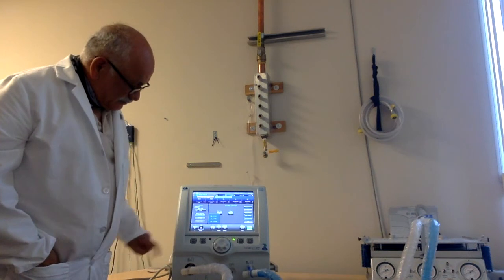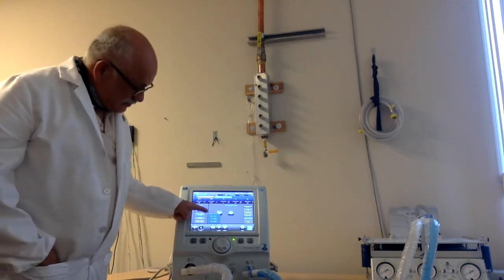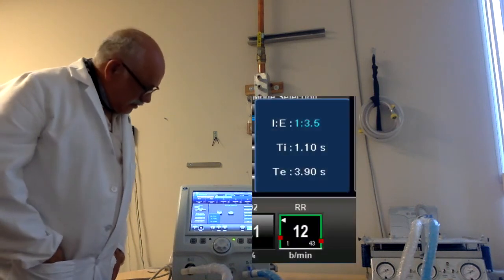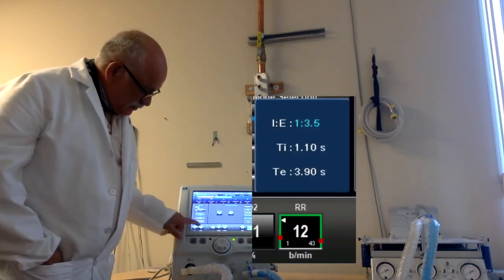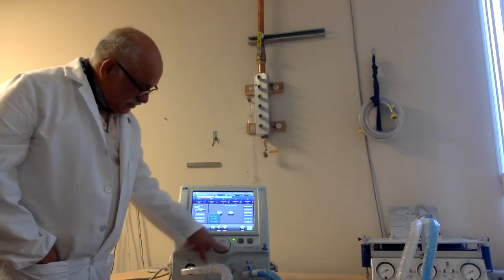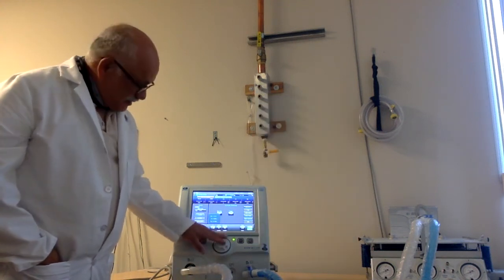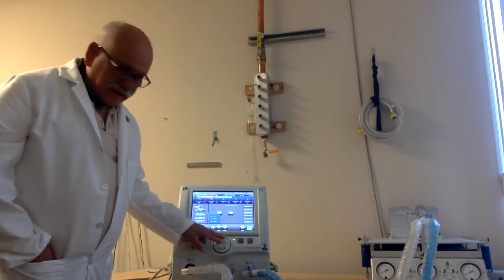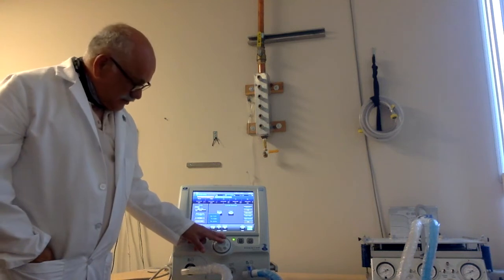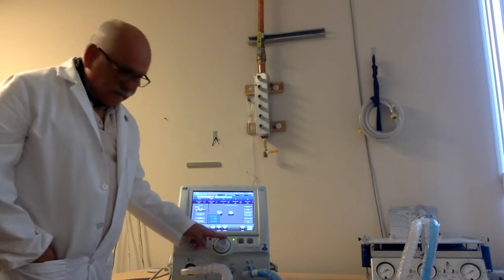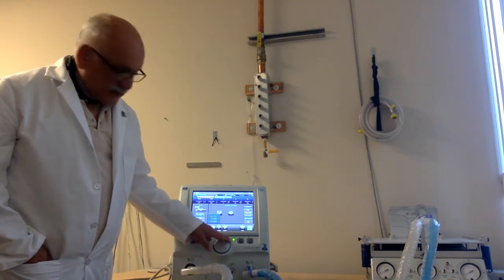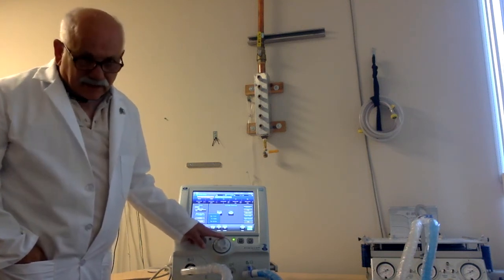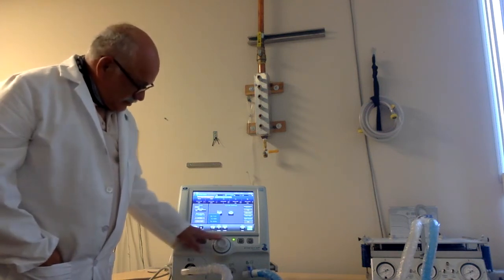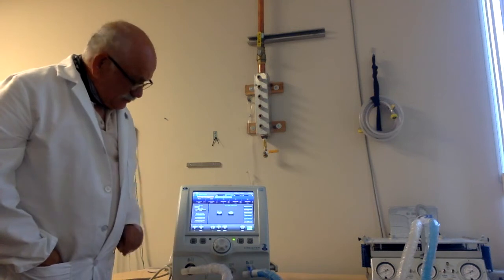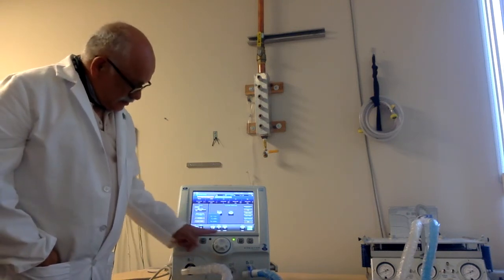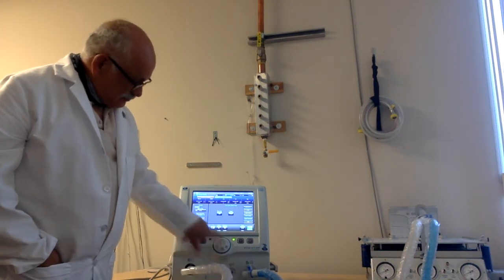I'm going to choose a rate. Now, when I want to choose a rate, you might notice that you see IE ratio, the time of inspiration, and the time of exhalation. As I rotate my choice of rate, I'm presented with the impact that will have on these variables: IE ratio, time of inspiration, and time of exhalation. This is important for physicians and therapists as they set a ventilator, to look at the impact prior to enacting it. Okay, I chose it. I'm going to go with a rate of 10. I did my touch, my turn, and my accept.